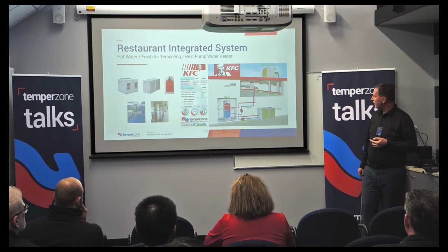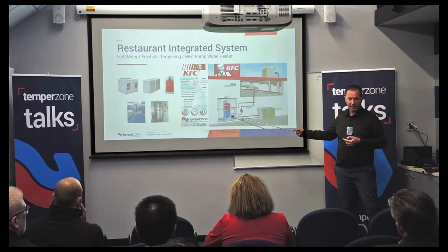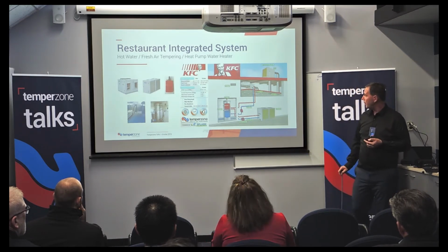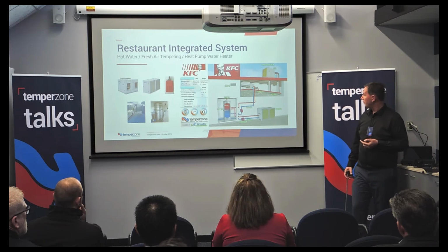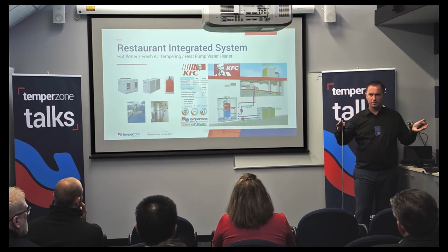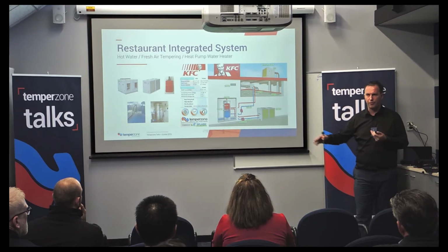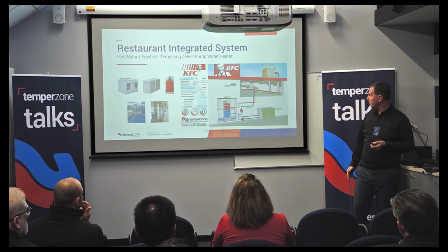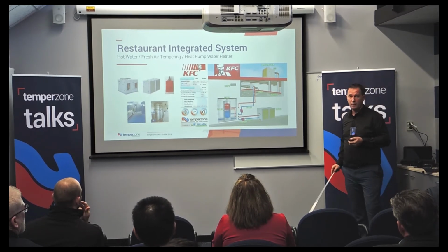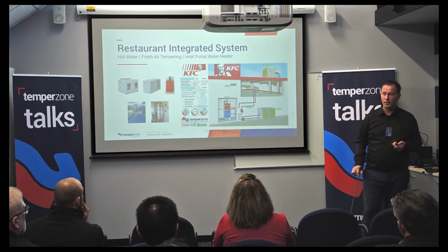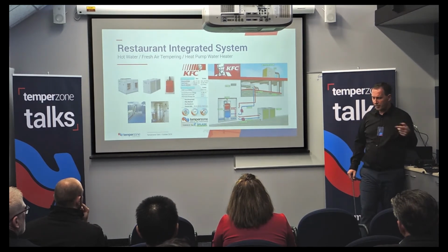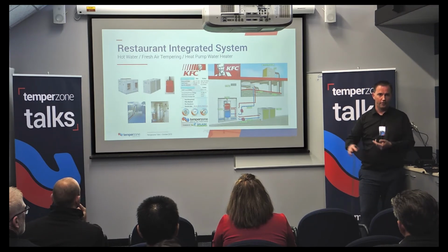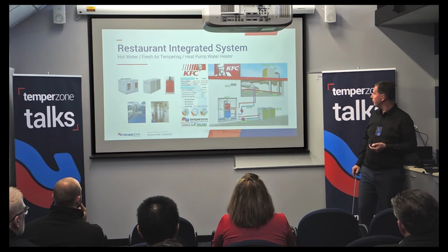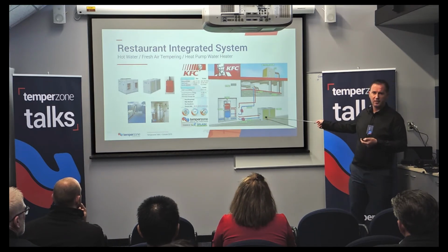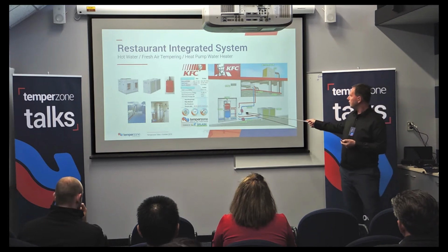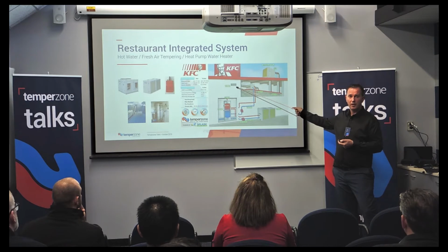So a KFC store has a large amount of potable hot water, which they in part use to defrost chicken. The water is used in about 400 litre batches about 3, 4, 5 times a day, depending how busy it is. And it also has a large fresh air temper load. If you don't temper the air, the food goes cold at the counters as it's being made. So we've used the spare capacity of the heat pump to supply the fresh air temper demand.